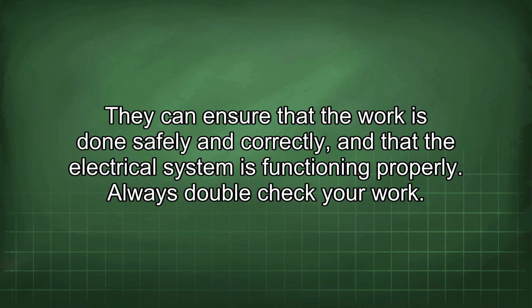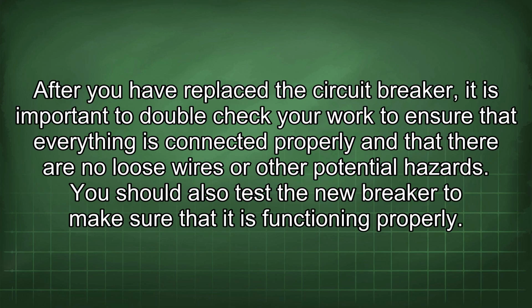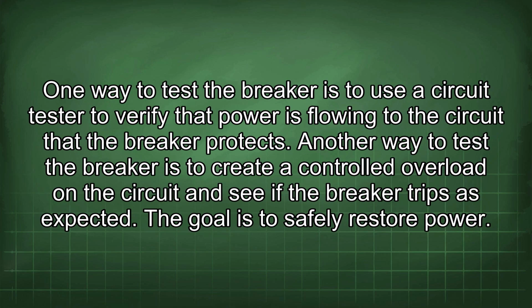Always double-check your work. After you have replaced the circuit breaker, it is important to double-check your work to ensure that everything is connected properly and that there are no loose wires or other potential hazards. You should also test the new breaker to make sure that it is functioning properly. One way to test the breaker is to use a circuit tester to verify that power is flowing to the circuit that the breaker protects. Another way to test the breaker is to create a controlled overload in the circuit and see if the breaker trips as expected. The goal is to safely restore power.